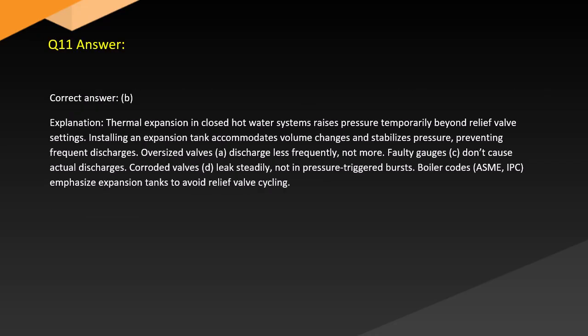Answer. Correct answer. B. Explanation. Thermal expansion in closed hot water systems raises pressure temporarily beyond relief valve settings. Installing an expansion tank accommodates volume changes and stabilizes pressure, preventing frequent discharges. Oversized valves, A, discharge less frequently, not more. Faulty gauges, C, don't cause actual discharges. Corroded valves, D, leak steadily, not in pressure-triggered bursts. Boiler codes, ASME, emphasize expansion tanks to avoid relief valve cycling.